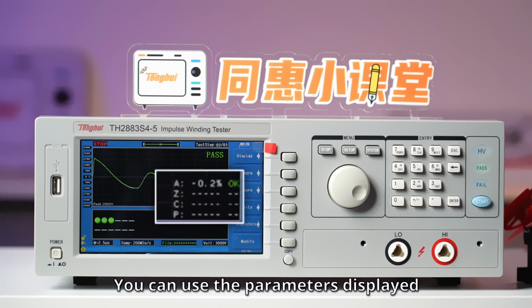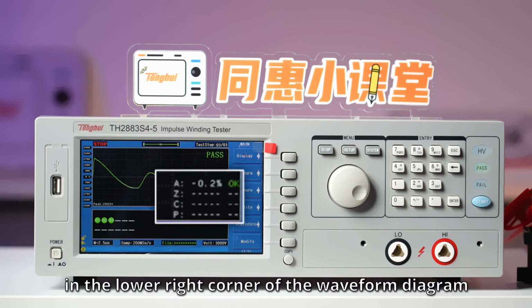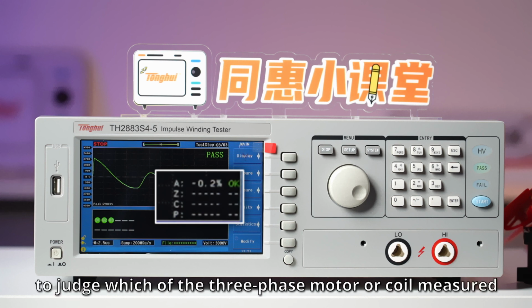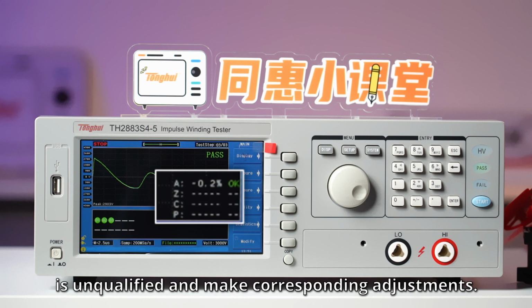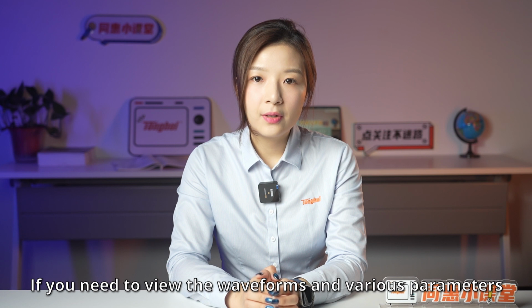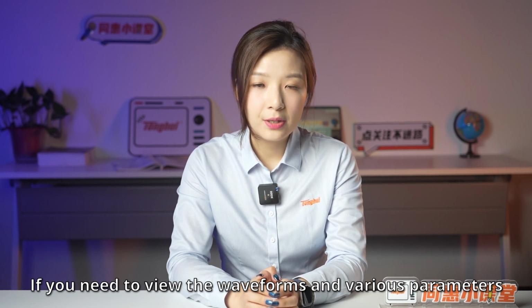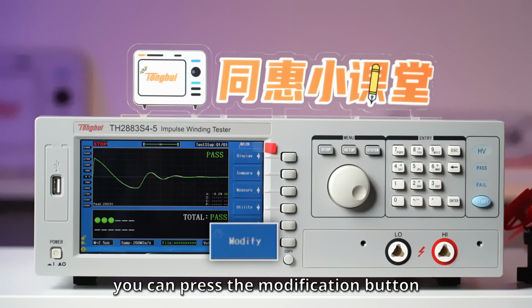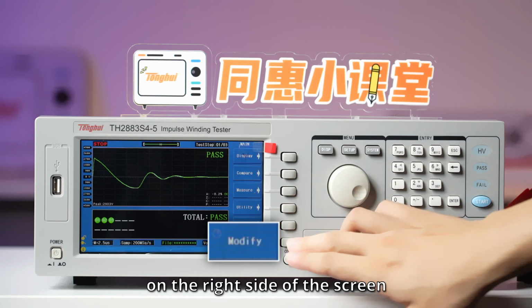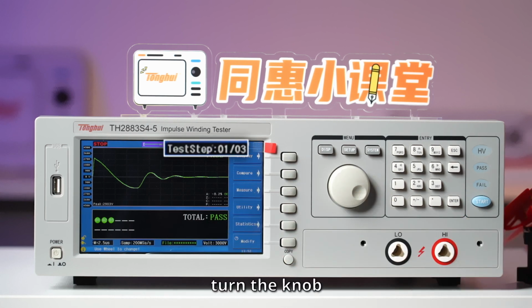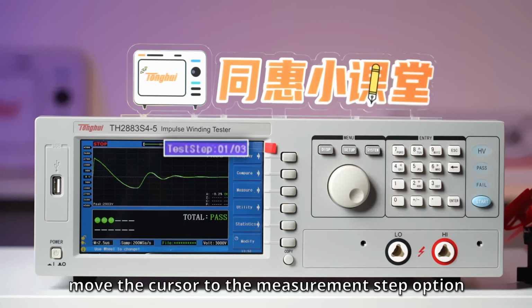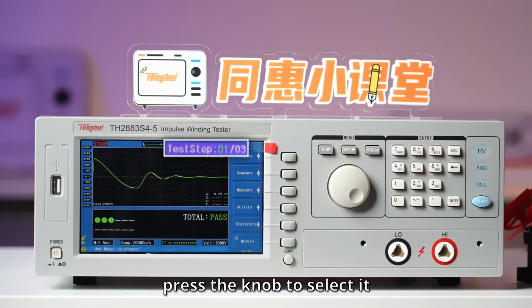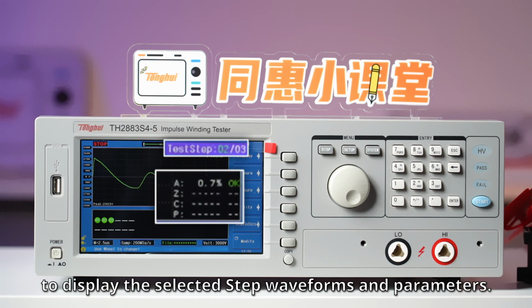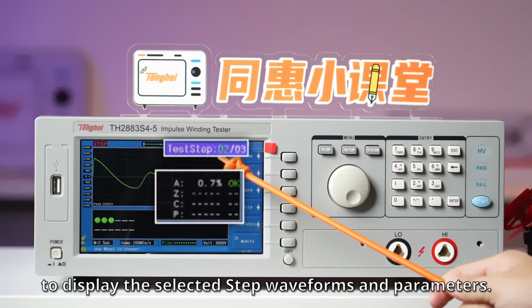You can use the parameter displayed in the lower right corner of the waveform diagram to judge which of the 3-phase motor or coil measured in the current step is unqualified and make corresponding adjustments. If you need to view the waveform and various parameters of the other 2 steps, you can press the Modification button on the right side of the screen. Turn the knob, move the cursor to the measurement step option, press the knob to select it, and turn the knob again to display the selected step waveform and parameters.